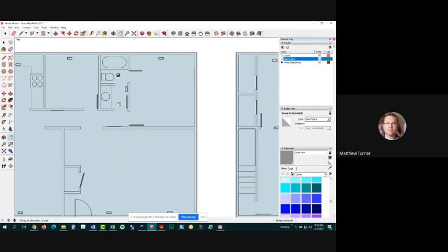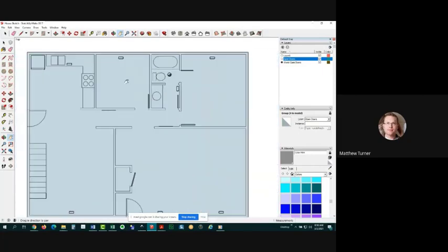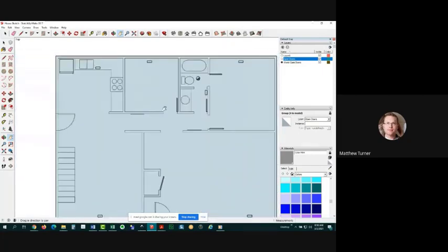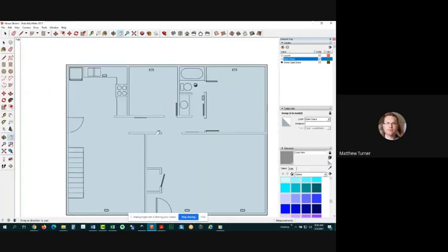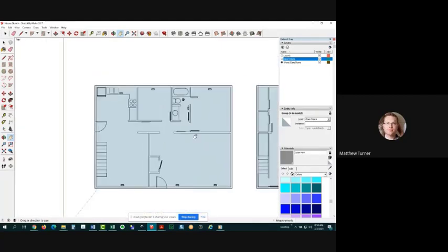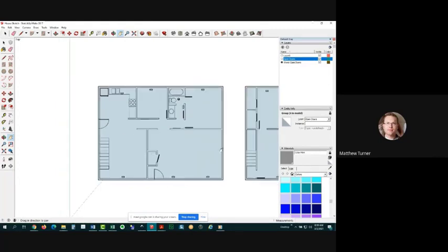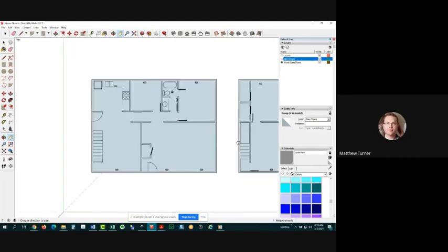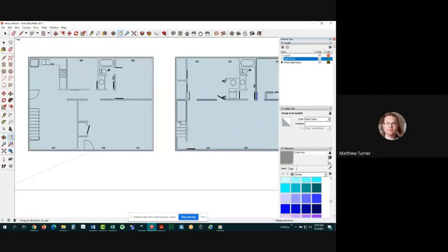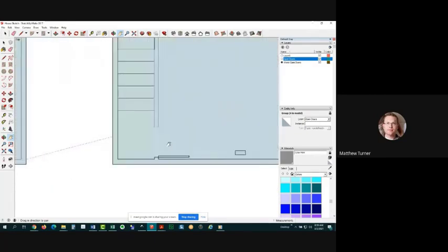We left this door open on this bathroom because it had an exhaust fan. We closed this bedroom door here. And then we didn't have any other doors to close upstairs. But we still have this large area upstairs with some central returns in it. And we really don't know how that's going to impact the pressure until we start closing that central partitioning door.